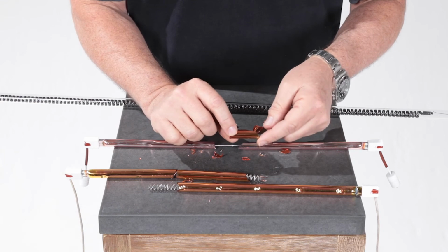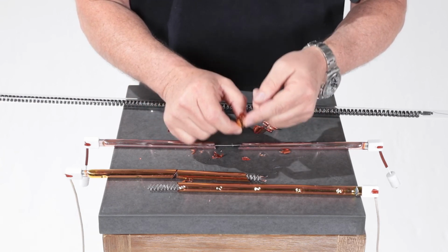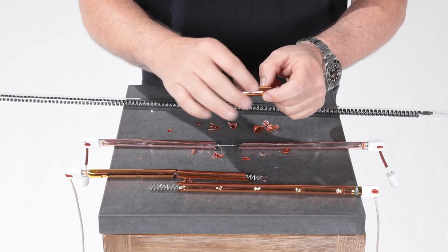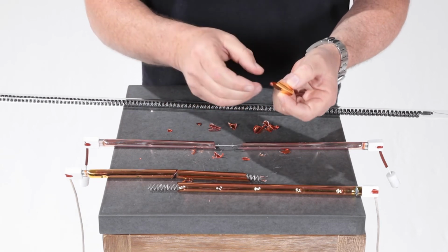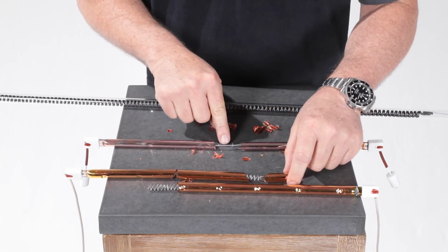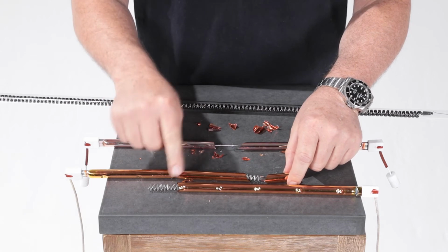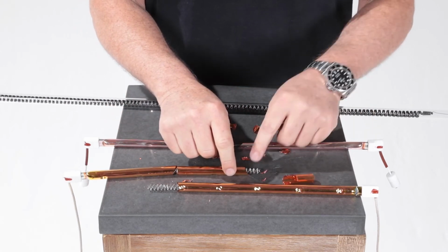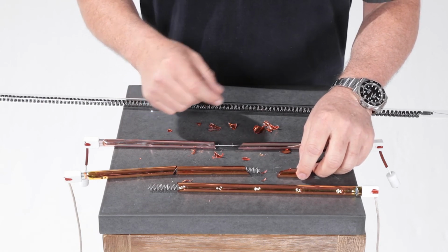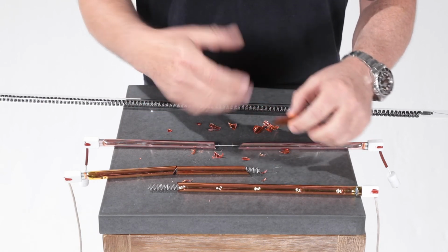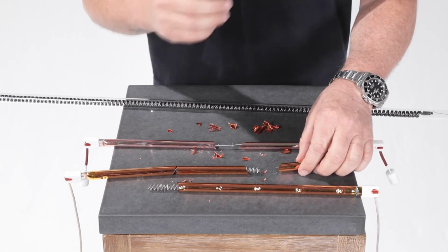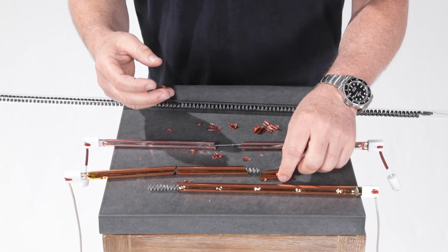So we've got a piece of the glass tubing here. It's actually clear glass, it's quartz glass. And then on the outside, we've got this gold coating. The gold coating reflects the heat on the inside, or reflects the light on the inside, and keeps the light in. So on these two different types of lamp, this is our standard tungsten lamp. And then this tungsten filament here, with the one with the squiggly line on it, is our latest ULG Plus style lamp. And that, with the coating on the top, cuts out something like 99.9% of the light. So very, very dim, gives out hardly any light at all.